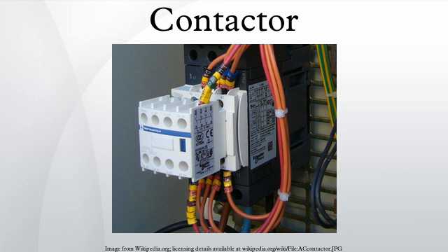Because arcing and consequent damage occurs just as the contacts are opening or closing, contactors are designed to open and close very rapidly. There is often an internal tipping point mechanism to ensure rapid action. Rapid closing can, however, lead to increased contact bounce, which causes additional unwanted open-close cycles. One solution is to have bifurcated contacts to minimize contact bounce. Two contacts designed to close simultaneously, but bounce at different times so the circuit will not be briefly disconnected and cause an arc. A slight variant has multiple contacts designed to engage in rapid succession.